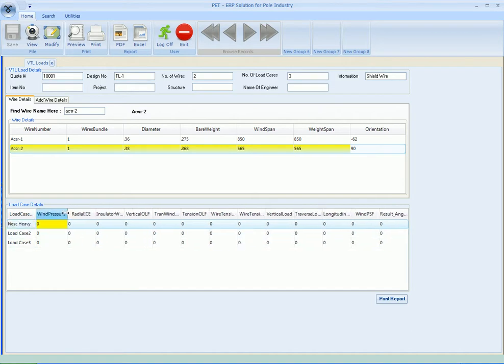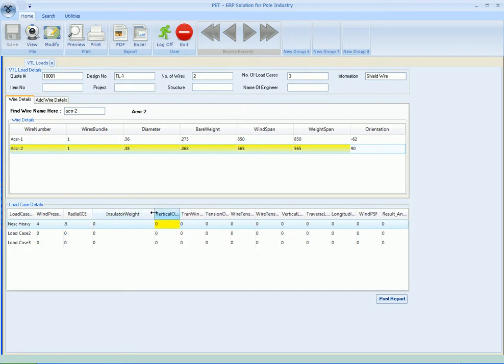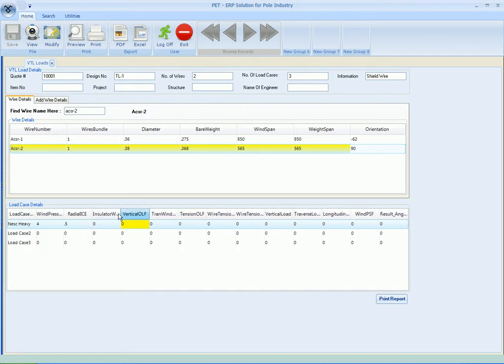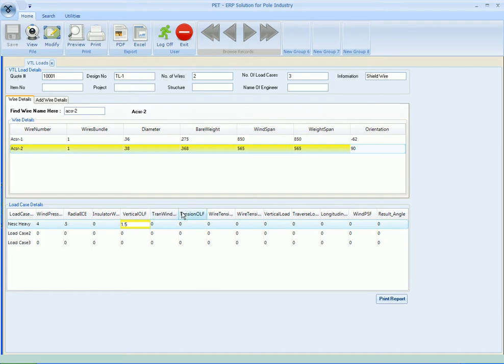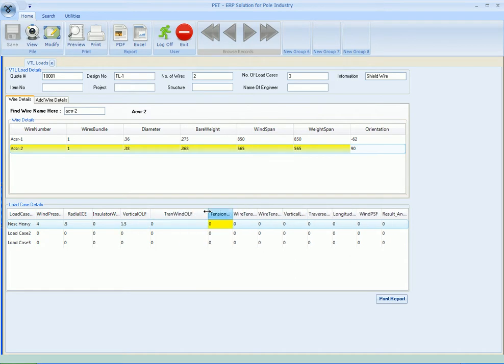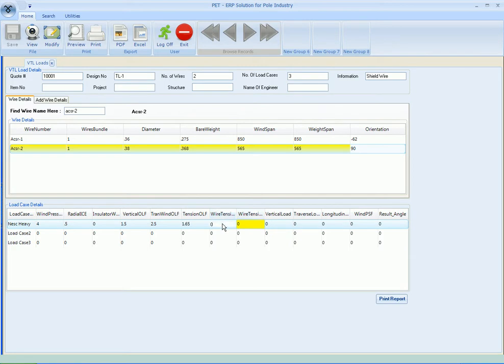Here is the detail for the load case - wind pressure for the first load case let's say 4, radial ice 0.5, and the insulator weight remains 0. Vertical OLF for the NESC heavy 1.5, the transverse wind OLF is 2.5, and the tension OLF is 1.65.